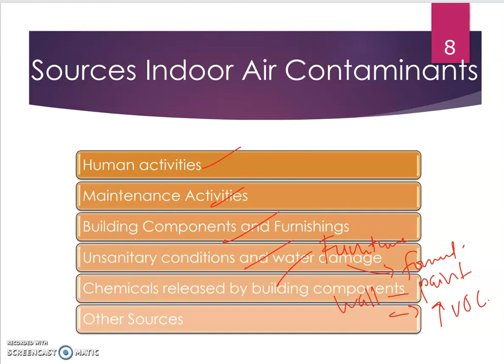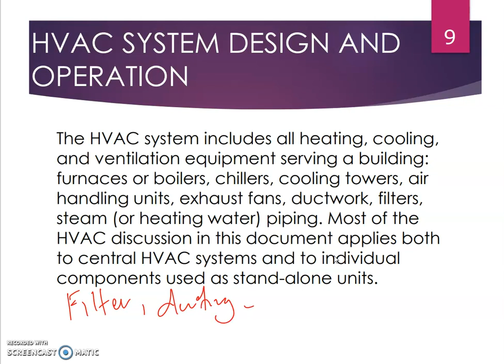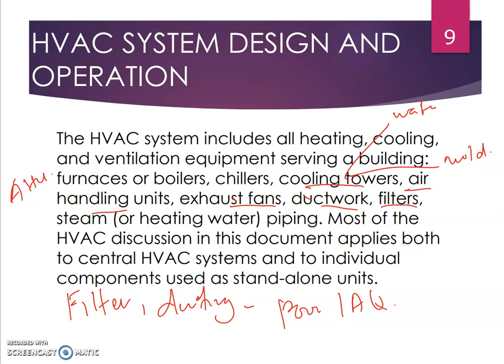So, HVAC system design and operation. Usually from the HVAC system, on the maintenance side, we have to make sure we change our filter, and then the ducting side, otherwise it will lead to poor IAQ. So we must make sure we maintain our system very well, including the cooling tower system, which is the water level. If we do not reject our heat well enough from the cooling tower and condenser side, your cooling coil will be dirty because of mold growth at the cooling coil, because there is not enough rejection in our air conditioning system. So in our air handling unit, for example our AHU system, we have to change the filter, and the exhaust fan ductwork filters must also be changed. So the maintenance side of the HVAC system is very important.